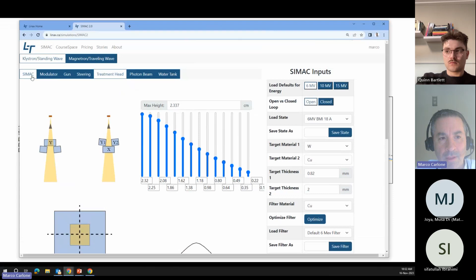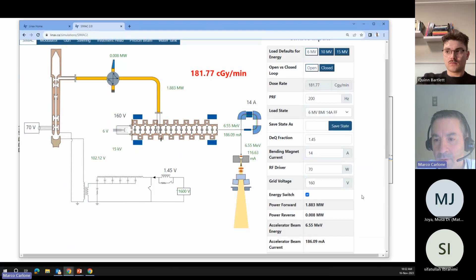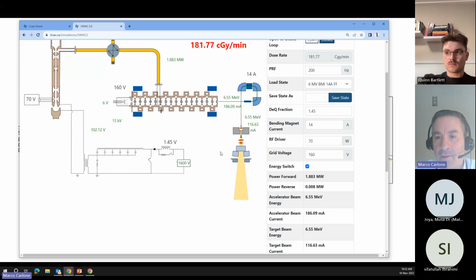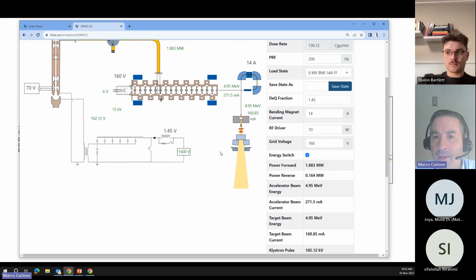I've configured some beams over here. So here is a 14 amp bending magnet current, including a flattening filter. If I go back and load this into the simulator, I can easily rerun this, because it's a simulation. On a real machine, teaching the same thing would be very difficult. There'd be a lot of work to first make sure that you're doing this safely, and then you'd have to undo it afterwards to make sure that you weren't changing the properties of the machine.